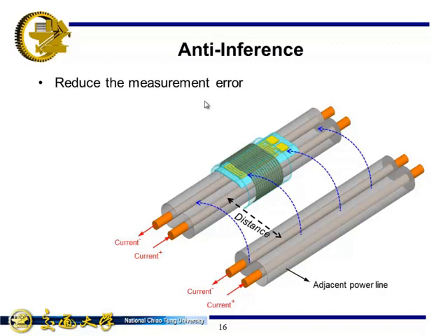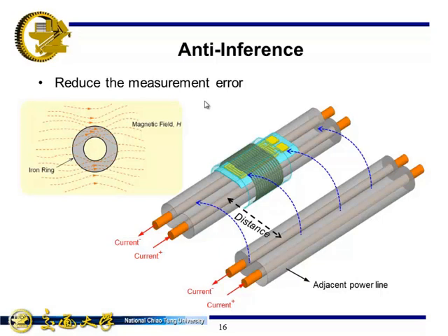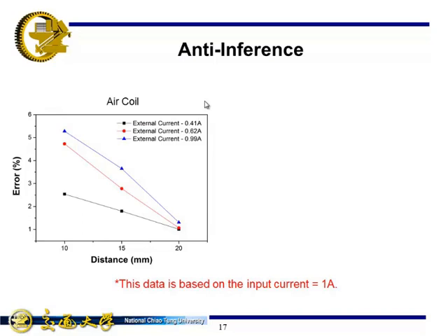Besides, the magnetic C-clamp has another advantage. When another power line is close to the source power line we measured, the magnetic field will also influence the current sensor. Therefore, the magnetic C-clamp can provide a function to block the outer magnetic field.